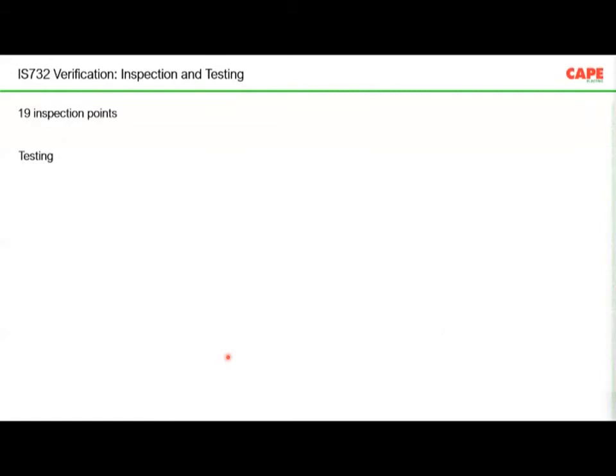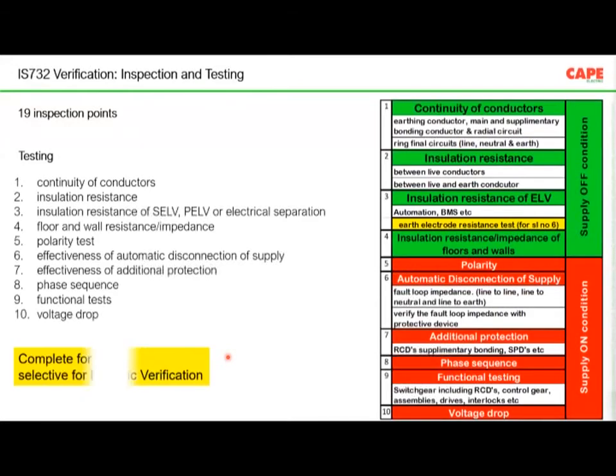What I wanted to tell you is that designing the electrical installation in a medical location is not that simple. You have to understand the standard and each and every requirement, and you should do it properly. And the final part is testing. In any hospital, the testing recommended in IS 732 for general locations is very much mandatory. There are 19 inspection points and about 10 tests. Of course, there is one more called PAT, portable appliance test. These tests are very much mandatory.